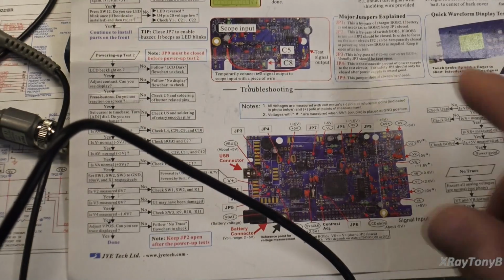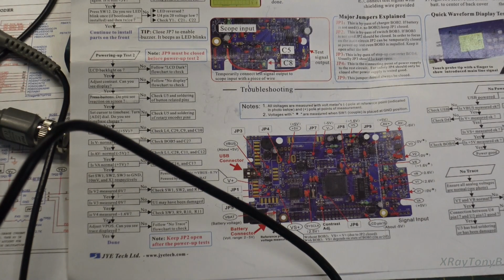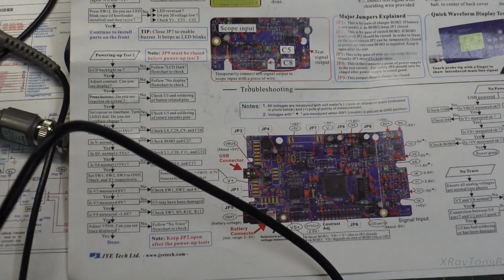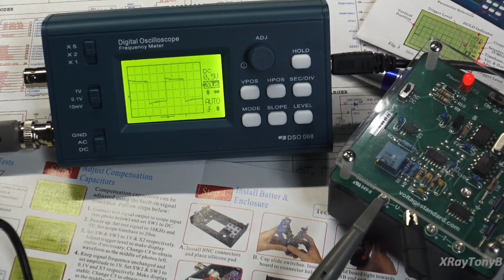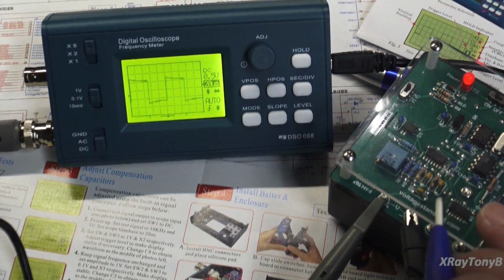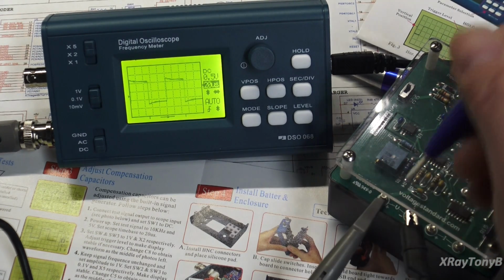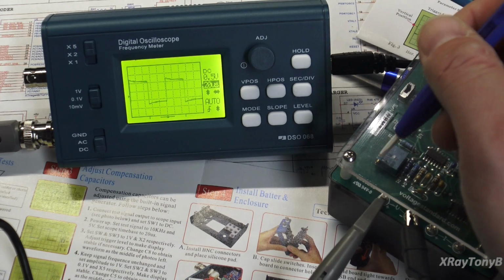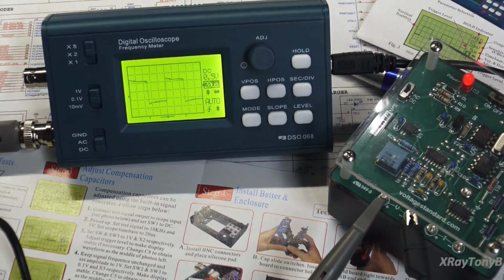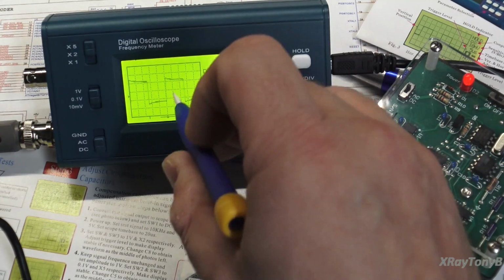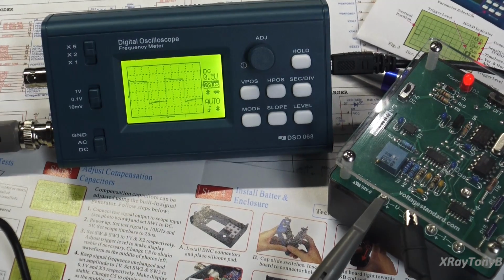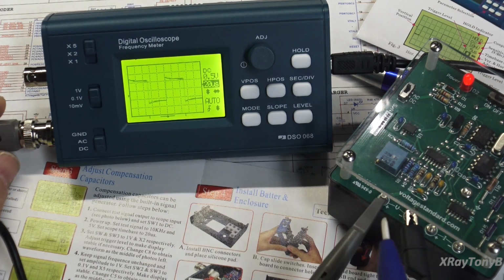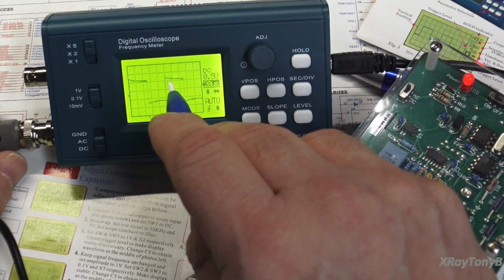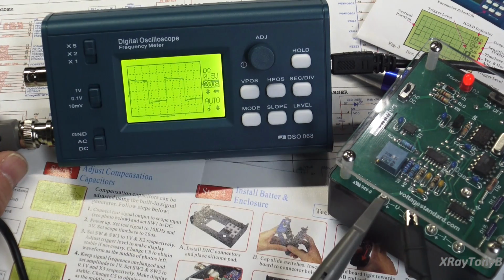Okay. Remove connection between test signal output and scope input. Adjustment is done. So they're saying that that's completely finished. I've now connected the scope back up to the test point, to our DMM Check Plus. I set the DMM Check to have a 10 kilohertz output at 5 volts peak to peak square wave. And as you can see, it's reading incorrectly. And I have the probe set on times 10 because this capacitor works on times 10. So what we want to do is adjust this for accuracy and for flatness.